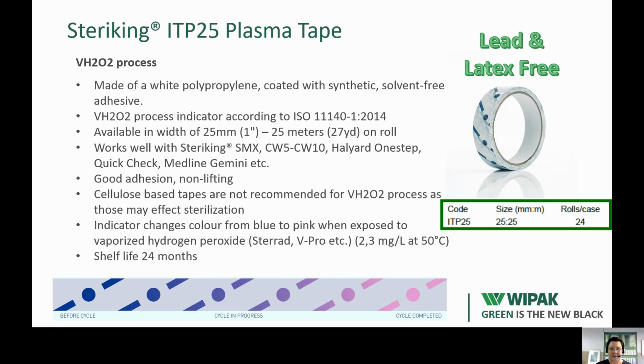Then as there is the increasing number of these low temperature hydrogen peroxide sterilization machines on the market, therefore it's also needed tape for those processes. So this hydrogen peroxide sterilization process, it's different in that respect that these paper-based or crepe-based tapes cannot be used in these processes because in worst case these tapes could abort the sterilization process due to the cellulose contained in their structure. So therefore only synthetic based materials are allowed to be used in this hydrogen peroxide sterilization process.